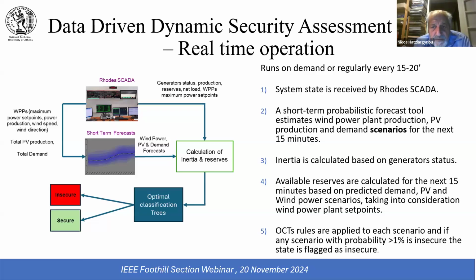For each scenario, based on the generators, you calculate the inertia and the available reserves for the next minutes, using the predicted demand and PV and wind power scenarios. Then you apply the optimal classification tree rules to see how the security of each scenario develops. If the probability is more than 1% that a scenario is insecure, the state is flagged as insecure.